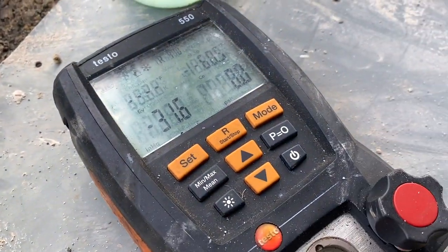It has been 25 minutes since I've turned the vacuum pump off. We are holding at a steady 31.9/31.6 because these gauges are junk. I got them wet and they tend to whack out on me a bit, but that seems to be a good enough vacuum for me. It seems like it's holding.